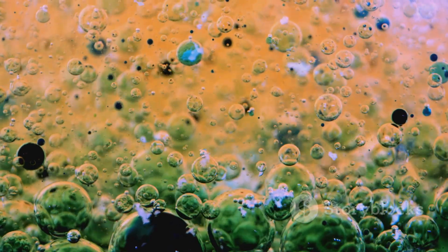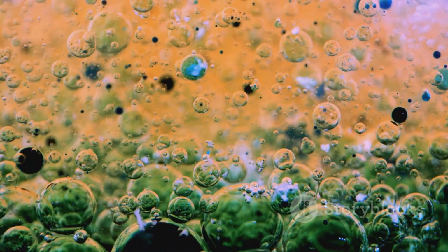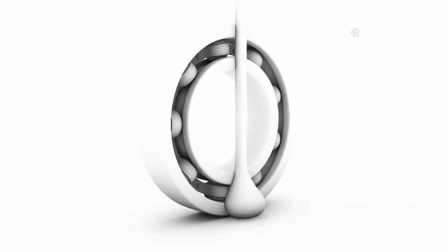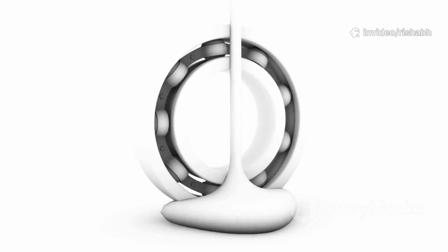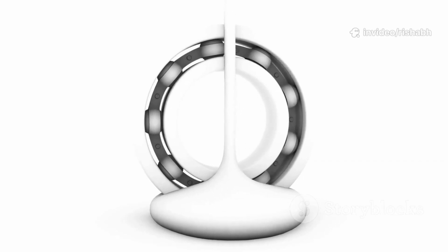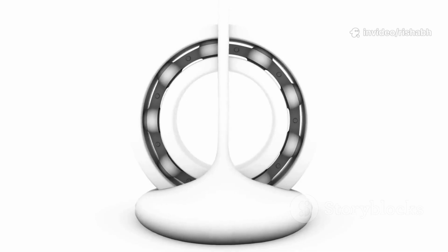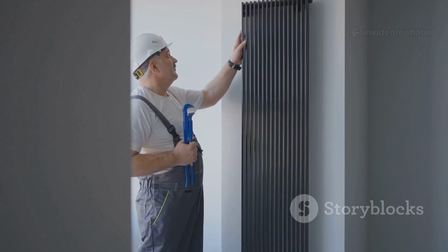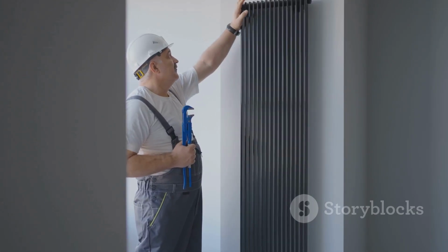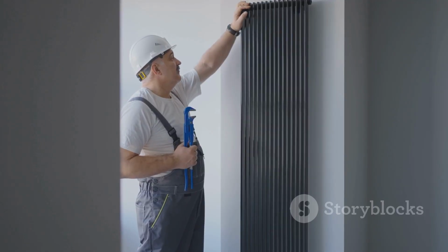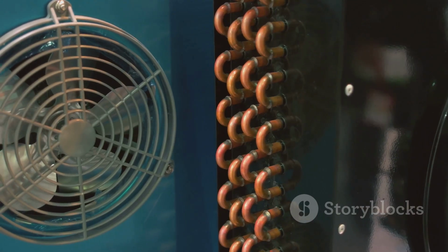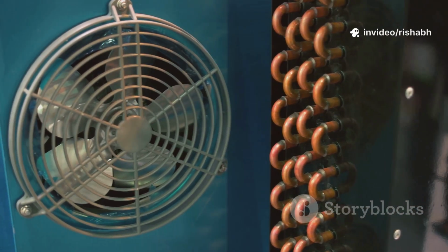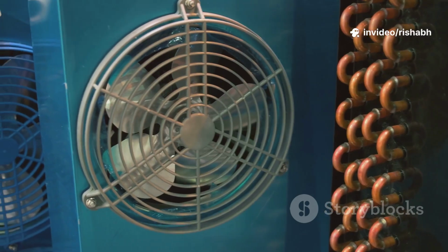As the oil heats up, it becomes less dense and rises to the top of the tank. Cooler, denser oil from the bottom of the tank sinks to take its place. This natural convection, a process known as thermosiphon, creates a continuous circulation of oil. This moving river of oil carries the heat away from the core and windings to the tank walls and radiators, where it can be dissipated into the surrounding atmosphere.